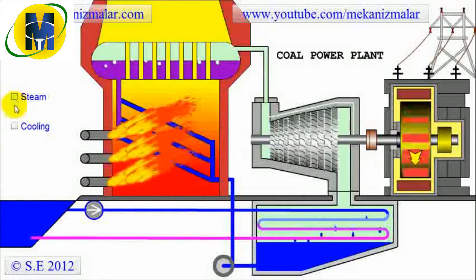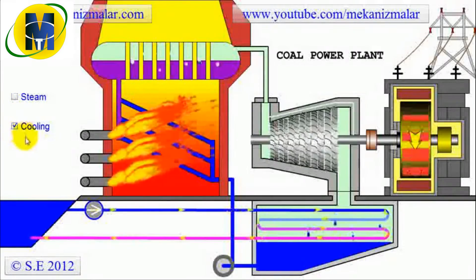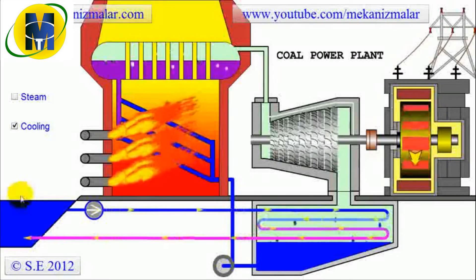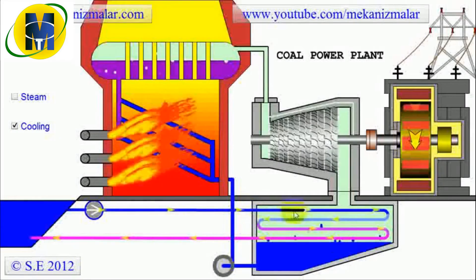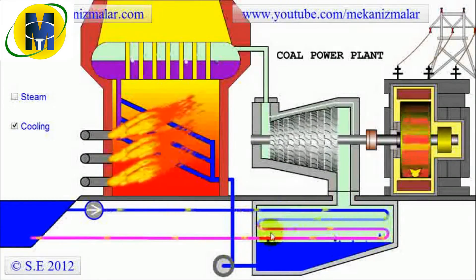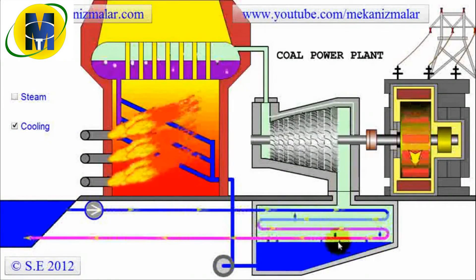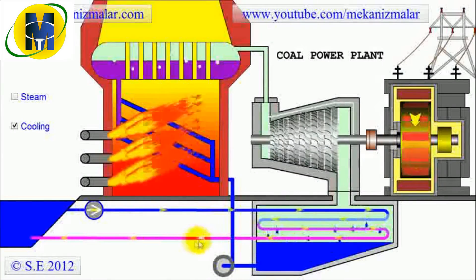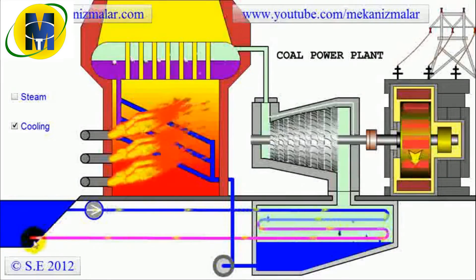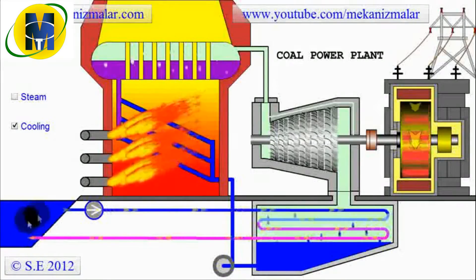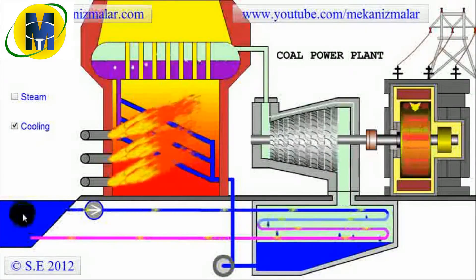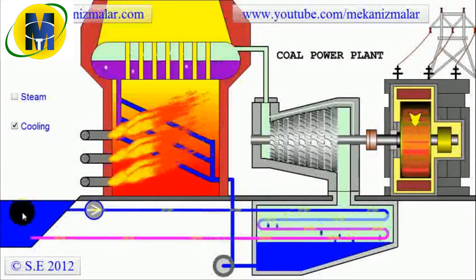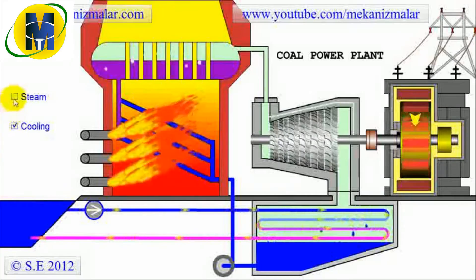Now let's discuss the second cycle, the open loop cooling cycle, which starts by pumping cold water from the upstream section of the river into the condenser inside the steel tubes. While saturated steam is condensed to water, the water from the river is heated. The heated water is then dispensed to the downstream section of the river. To protect ecological stability of the river, the temperature rise should be kept to a minimum.